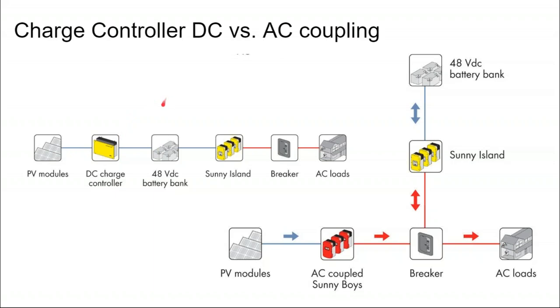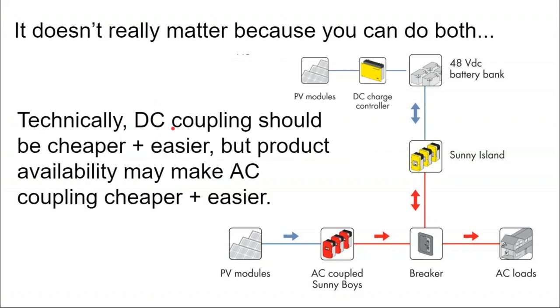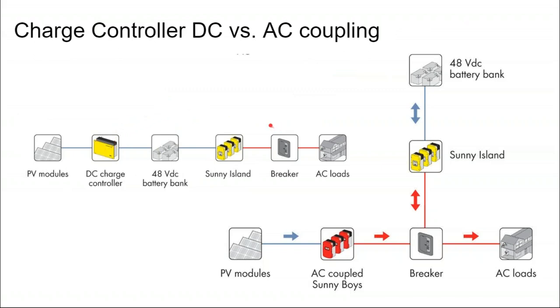The purists say DC has some technical advantages, about black-starting the solar array. The problem is, when you AC couple and the sun goes down, the solar inverter needs to be able to see the grid to start back up again. And if your batteries fully drain and your battery inverter can't start up again, the solar array comes up, but your solar inverter is still off. So the danger is that with AC coupling, your solar array might turn off and not be able to turn back on again.